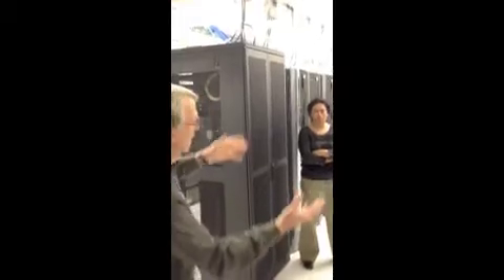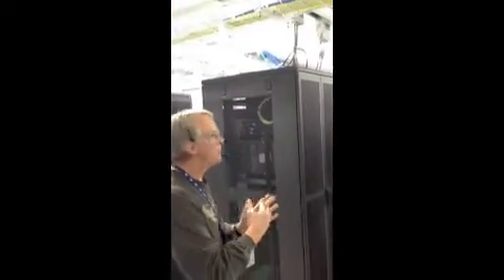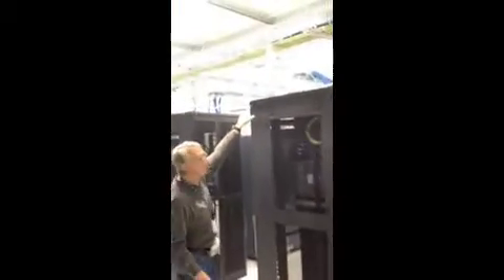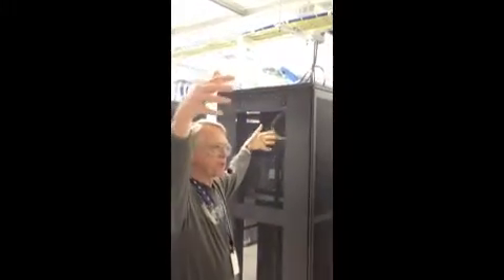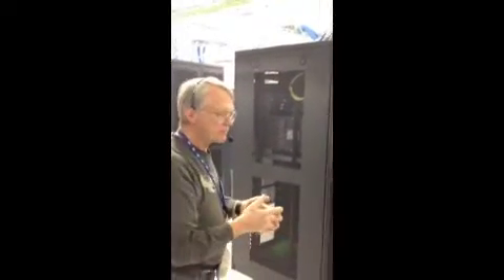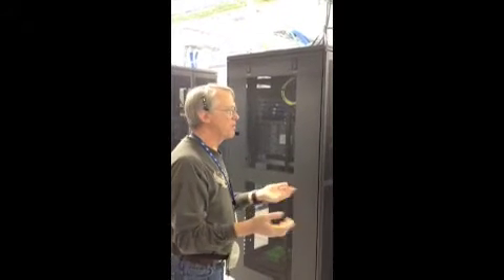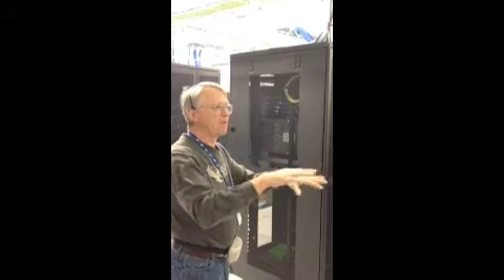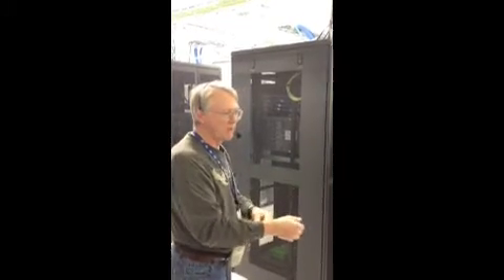So the plan is that the computer room air conditioners, these big gray boxes you see behind you, chill air, they blow it under the floor, it comes up through the grates, and then the only path to get back is through the rack, because the plastic curtains block any other path. And then it goes up through the grates you see in the ceiling. And the ceiling is basically a big return air plenum, goes back into the CRAC air intakes where it's chilled again and comes back out. The CRACs themselves are operated with chilled water. The chilled water is typically supplied by the evaporative coolers outside, and that's another part that we're going to visit.